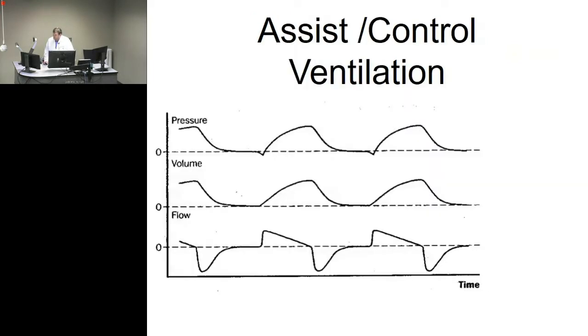Okay, so this is what you're going to walk into otherwise when you get into a ventilator, and you're going to have 3 different curves, and they're always generally laid out in this order. I'm sure there are some ventilators that want to confuse you, but for the most part, you're going to have the top one being your pressure curve. Then you're going to have either your flow or your volume curve, and then below that, you'll have your flow or your volume curve. So these two get switched sometimes. In this case, we got pressure, volume, and flow. I think on the Maquet ventilators, it's pressure and then flow and then volume. But they'll always tell you up on the left-hand side what you're dealing with.